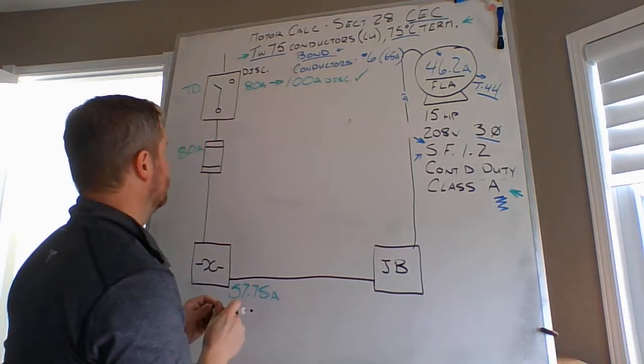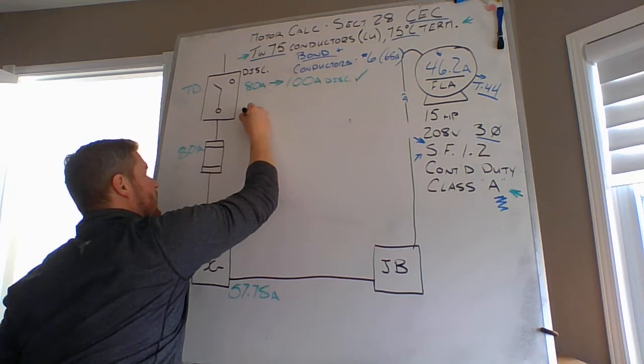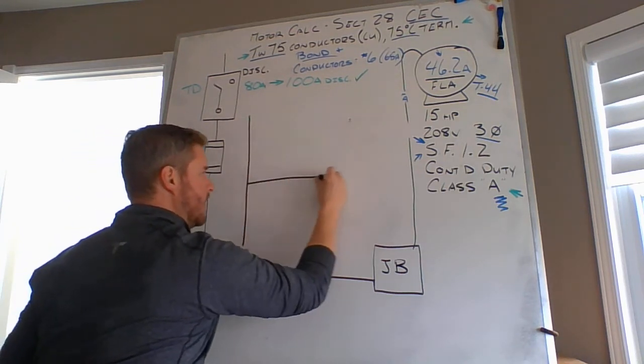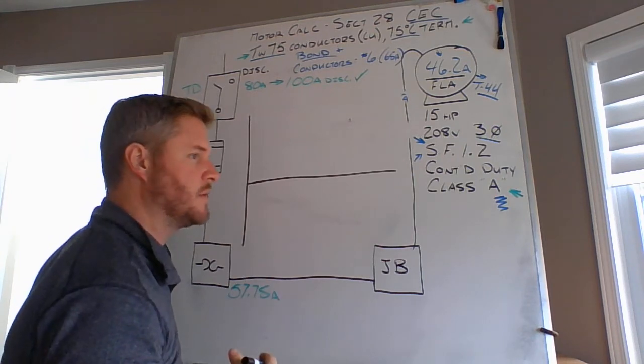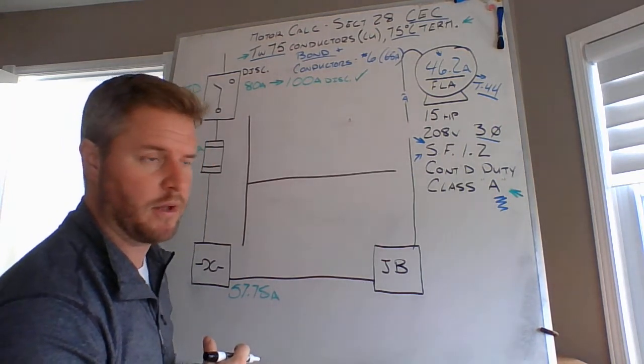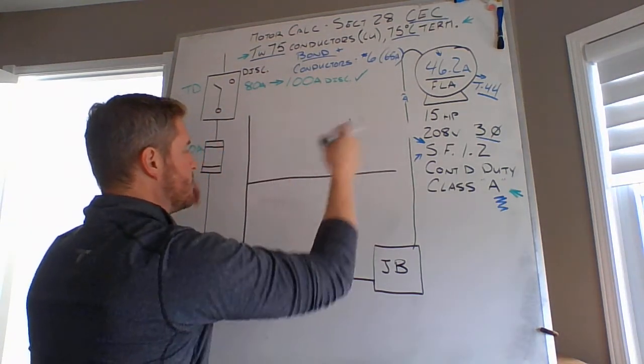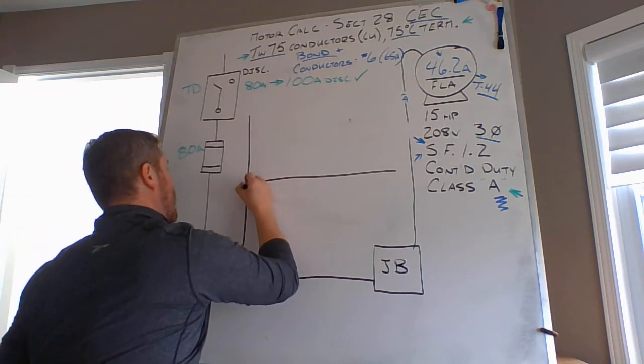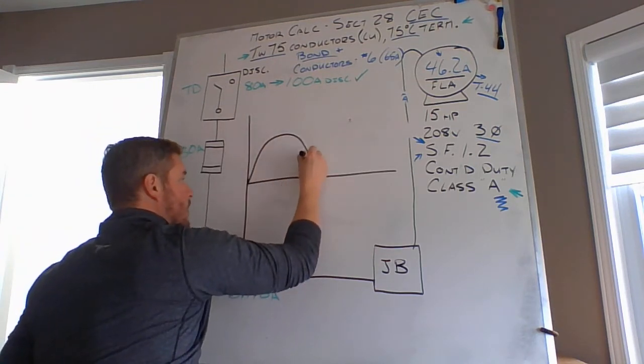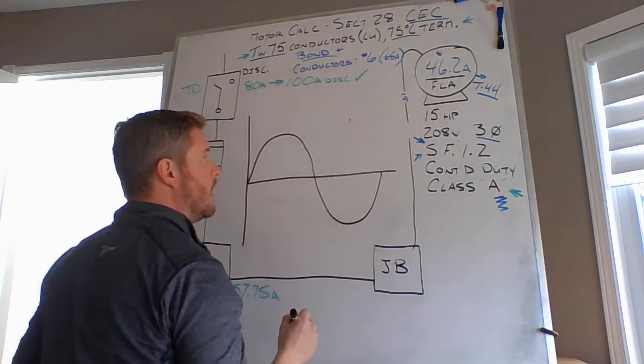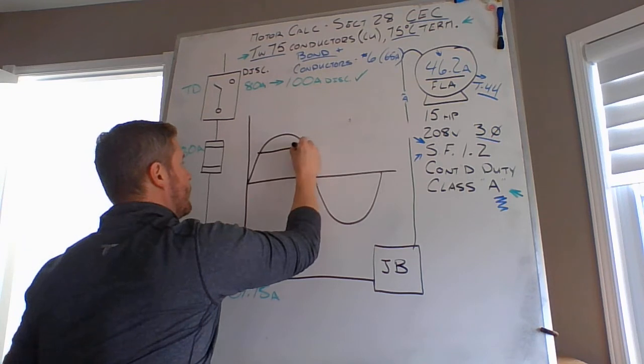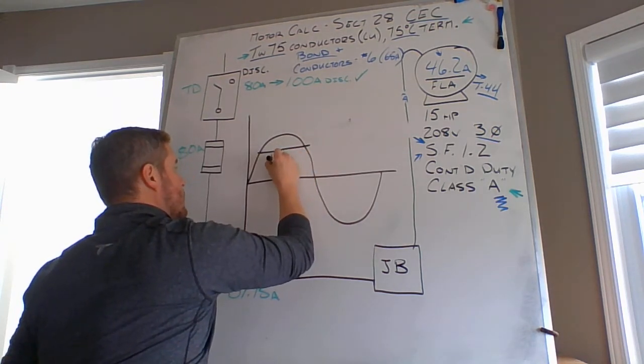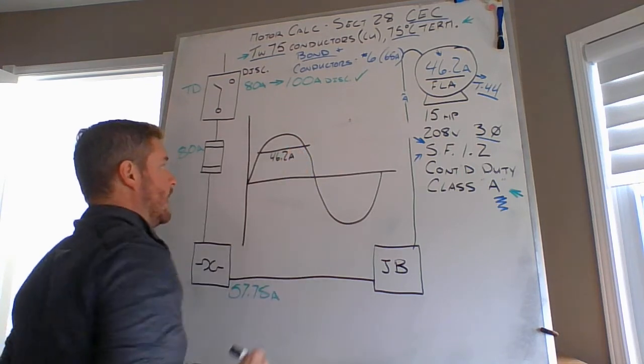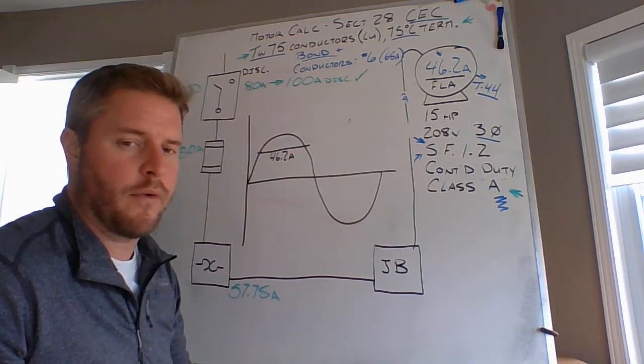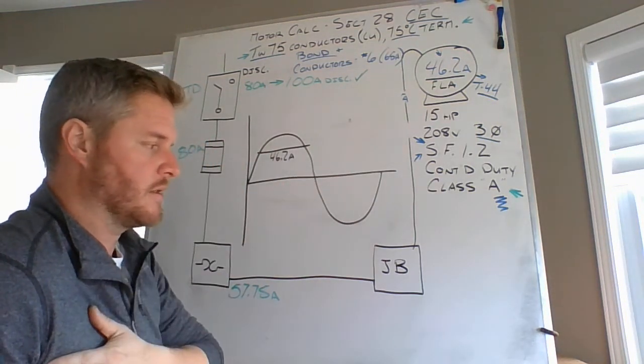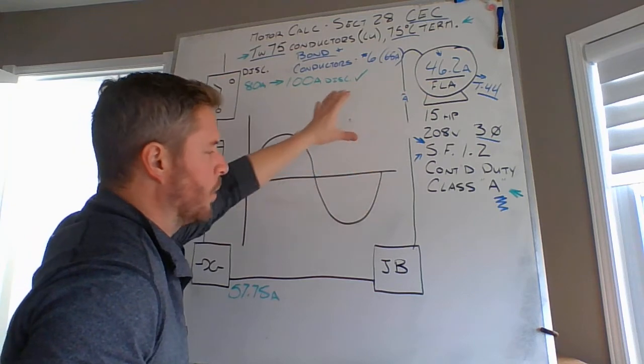When you use an oscilloscope, the majority of the time you're observing a voltage or voltage characteristics. You can use a channel on an oscilloscope to scope current at the same time as well. So if everything is going smoothly with this motor, and it's working at full capacity, you can scope your current to be an RMS value right here of 46.2 amps. A root mean square value of current, looking at an AC sine wave very similar to this. That means everything is going appropriately.